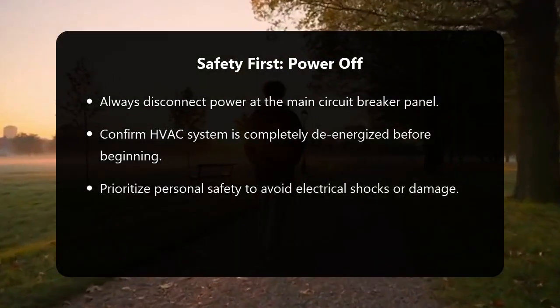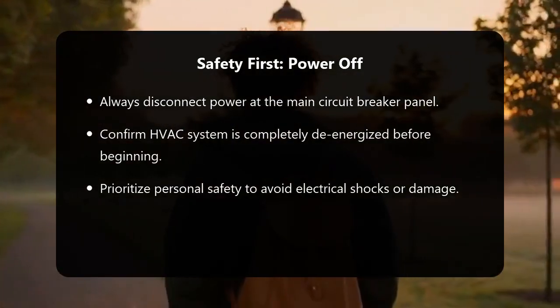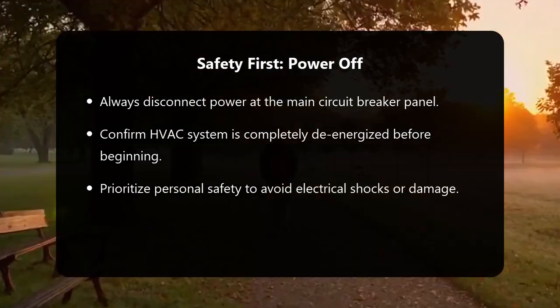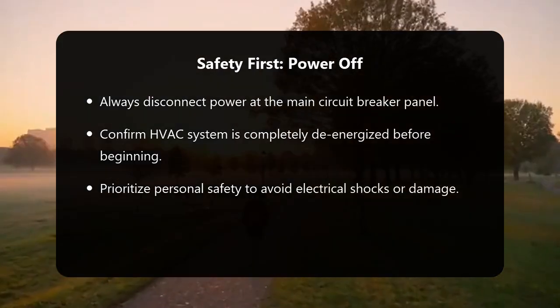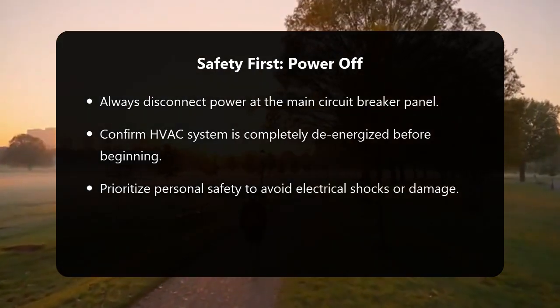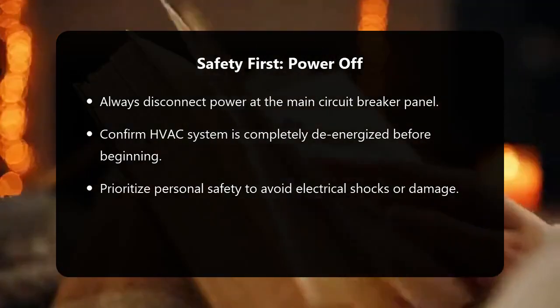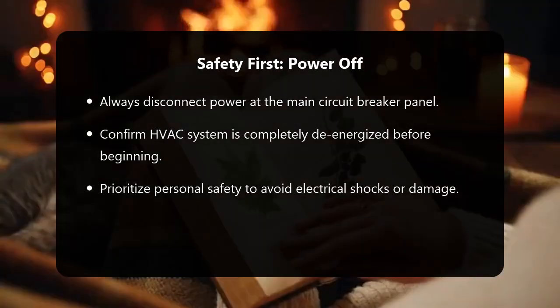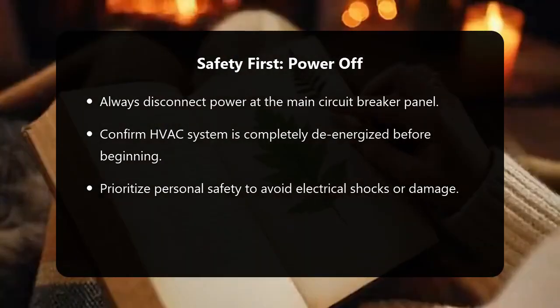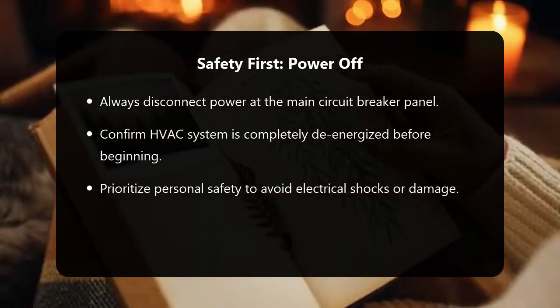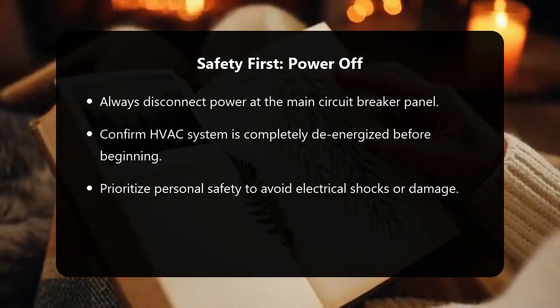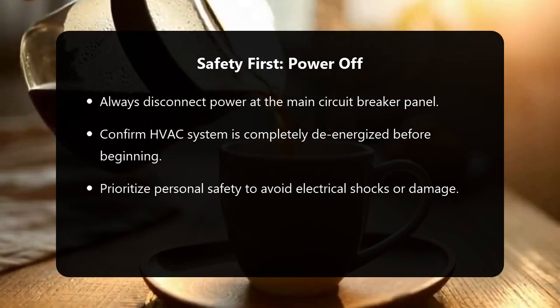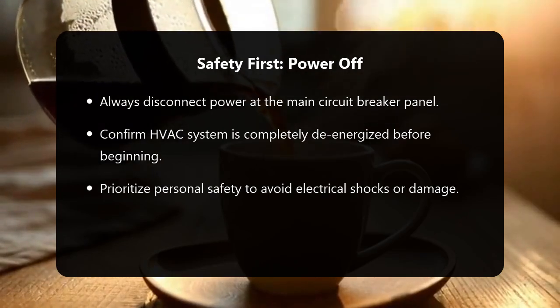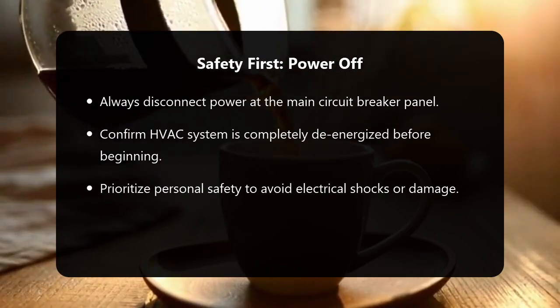Before you touch anything within your HVAC system, the absolute first and most critical step is to shut off power to your furnace or air handler at the main circuit breaker panel. This is a non-negotiable safety measure to prevent electrical shock or damage to your equipment. Confirm that the system is completely de-energized. You can try turning on the thermostat to see if anything responds. It shouldn't. Once power is confirmed off, gather your tools.